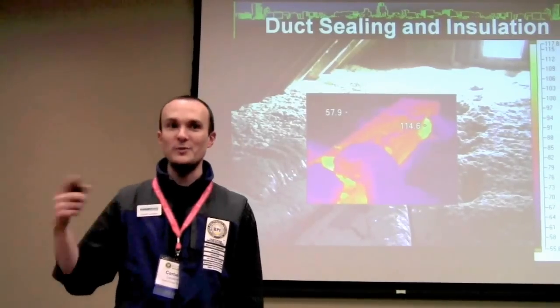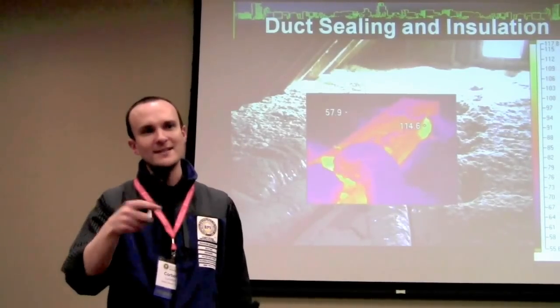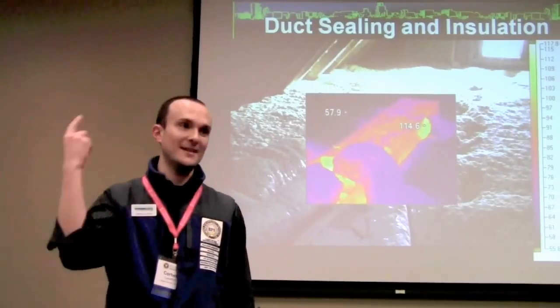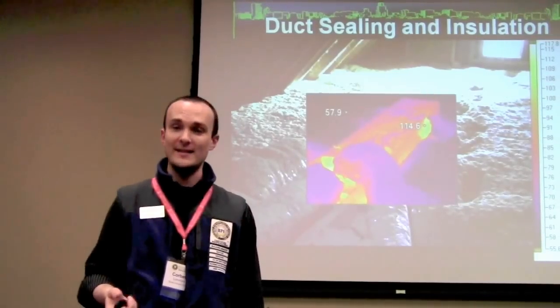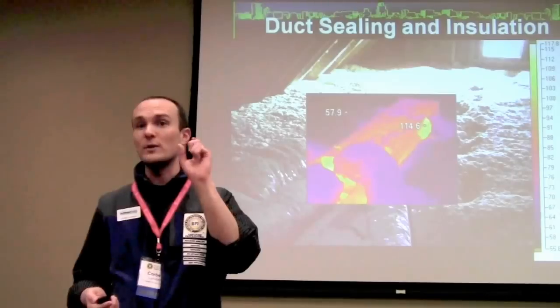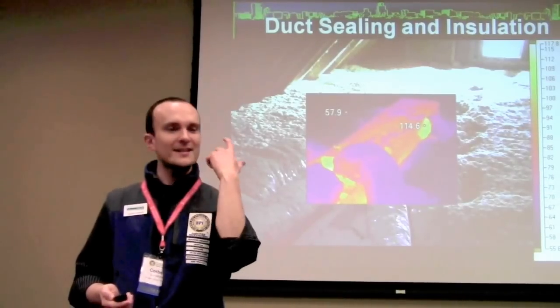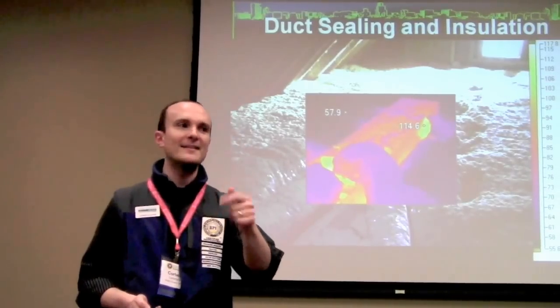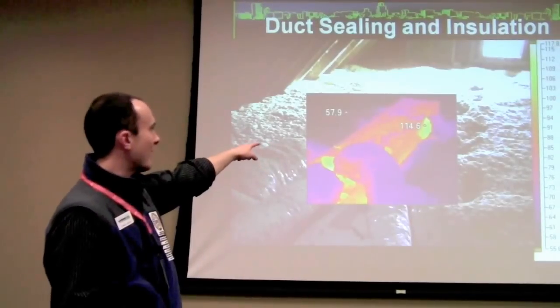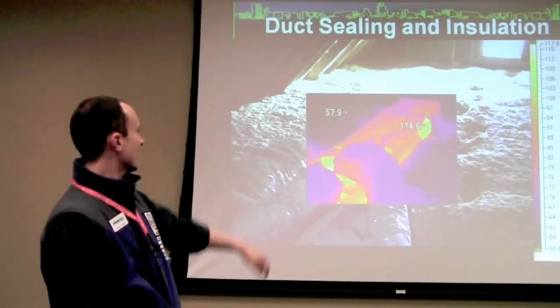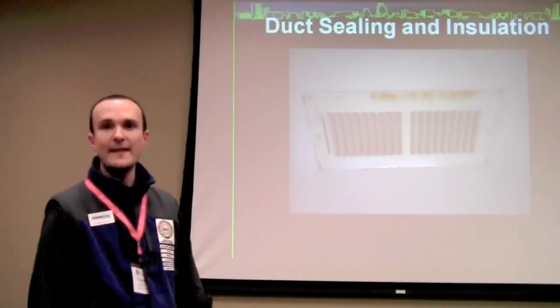Now, which one do we care about insulating? The house with a 50-degree delta T, or the ducts with a 110-degree delta T? Way more heat flow out of the ducts than out of the house if you think about it simplistically. That's another thing we're just not paying attention to sometimes when we've done work like this, and it results in that kind of thing.